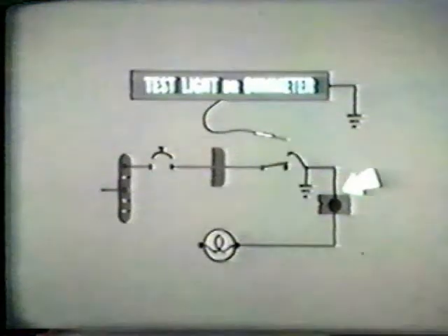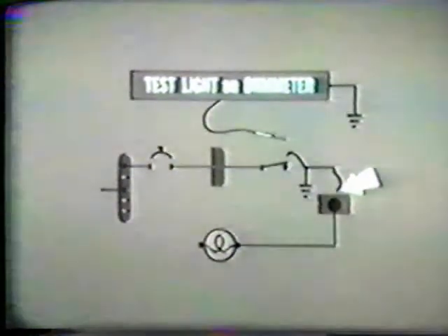We move on to the next wire junction and disconnect the two segments. When we test here, we will get results. The tester's light will glow or the ohm meter will show a reading. We know this wire is accidentally grounded since there's a complete circuit from it through ground. Two things have helped us to locate this electrical fault. First, careful reference to a wiring diagram. There's nothing which will help more in troubleshooting than a thorough study of a circuit's design before you go to work.